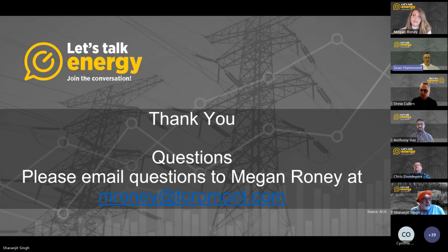Historically, the answer's been no. The reason being, when solar is grid-tied, if there's a power outage, there might be power line workers doing a repair on the lines, and the system is designed to shut off to protect them. In the case of a microgrid, though, that system could be designed to operate without the grid connection. So if I'm working with Toromont to design something with PV, we would typically be integrating a BESS and generator in that overall strategy. In that case, solar would be seeing its grid reference that it needs to operate from the BESS, and the controls that Toromont would implement would give the grid reference. So typically, a simple grid-tied solar system doesn't operate when the lights go out. But if by design that's been incorporated, then yes, it can.